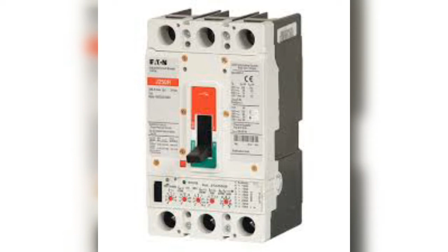It controls or cuts off a circuit during the operation of electrical devices and also protects the devices from damage. Both the short circuit making capacity as well as the short circuit breaking capacity of a circuit breaker must be larger than or equal to the prospective short circuit current at the place of installation.